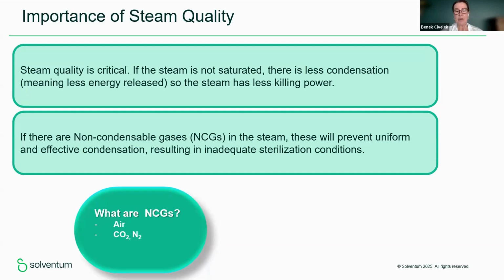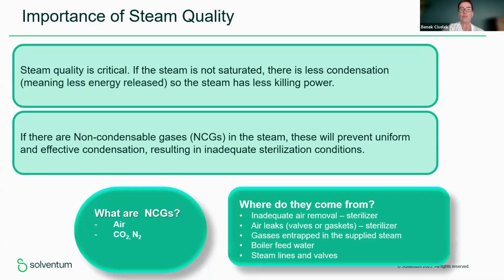There are various points where these come from. They can come from the vacuum pump, because if the vacuum pump does not work well, there will be air pockets inside the chamber. Also, inadequate air removal will leave these non-condensable gases and prevent effective condensation. There can be leaks due to the valves and gaskets, because the sterilizer is working all day and these pieces are working under pressure and higher heat. So these can also be another reason for non-condensable gases. Feeding water, as we all know, is always very important, and also the steam lines and valves. These all can create non-condensable gases, which we should prevent.